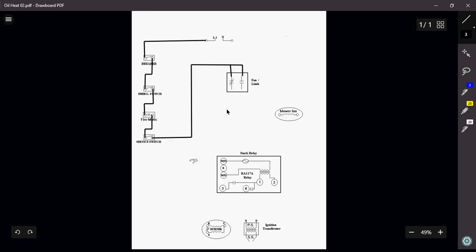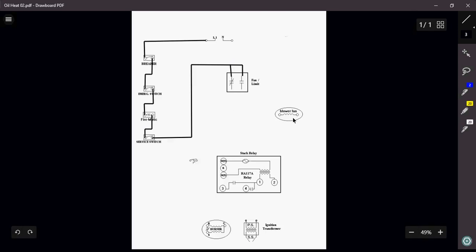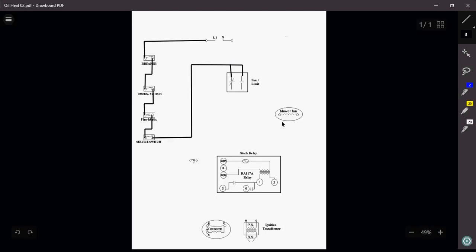So what I really want to do first is I want to focus just on the limit side of that fan limit switch. Now remember, the limit is a safety, so I want that to shut off my furnace if I happen to get too hot for whatever reason. Say we're overfiring, we got too big of a nozzle in there, maybe the blower fan doesn't come on, what have you.